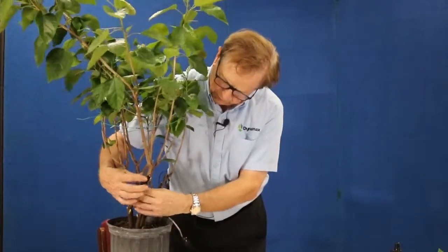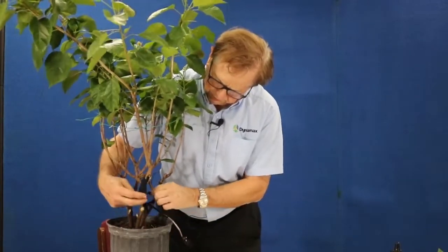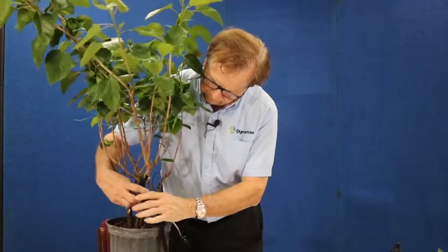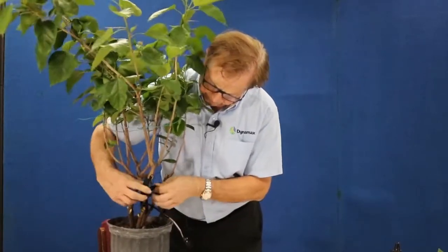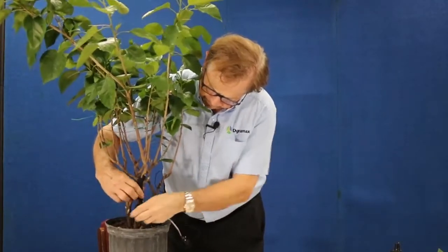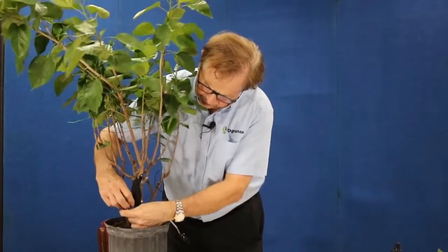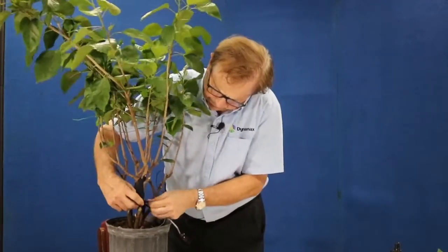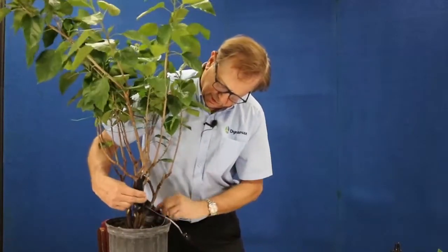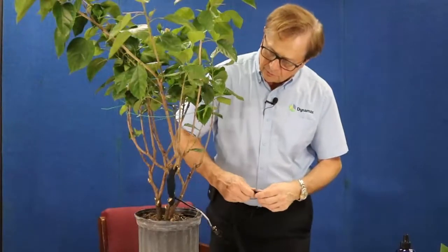Okay, now that I've got the upper part done, I can remove the double-sided Velcro and I can install the bottom part. Each time I'll stretch it a little bit. Then as I cover the sensor, I'll also strap the wiring to the Velcro. And that sensor is on there securely. I cannot move it with my fingers with an easy motion. Okay, let's start with the next step.